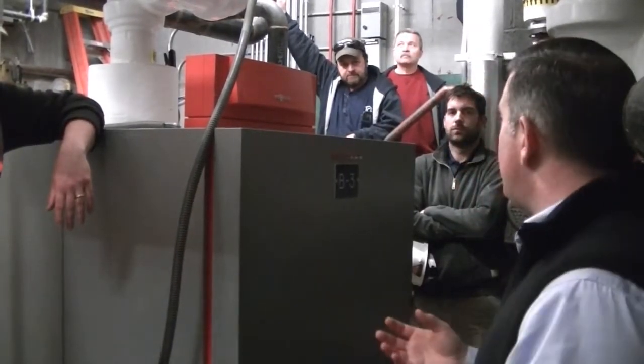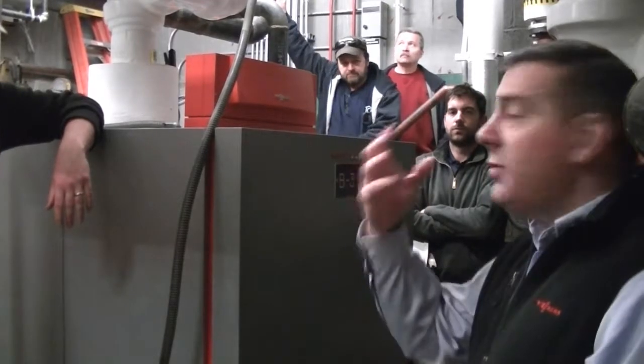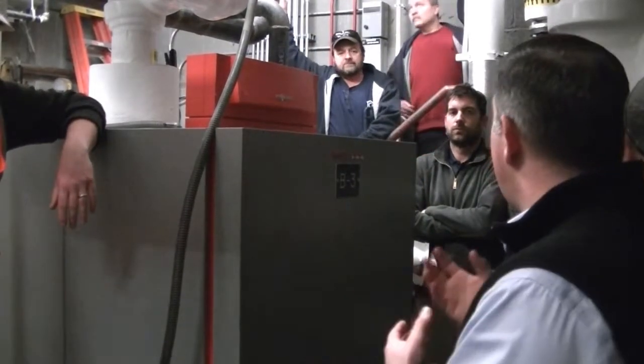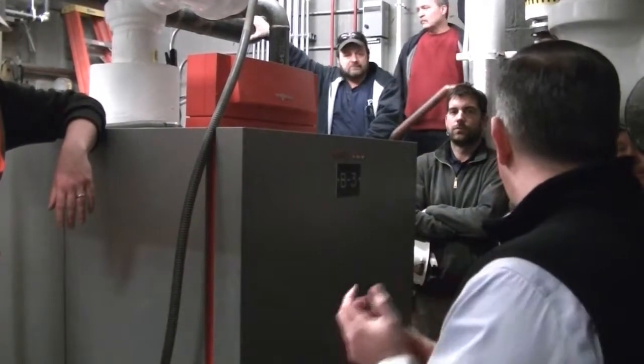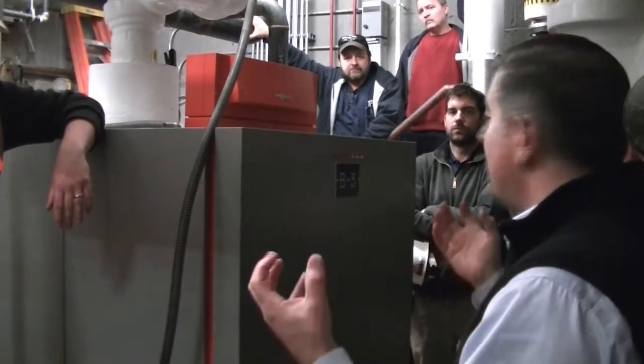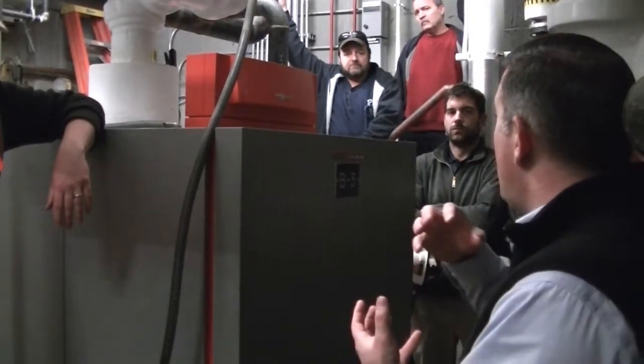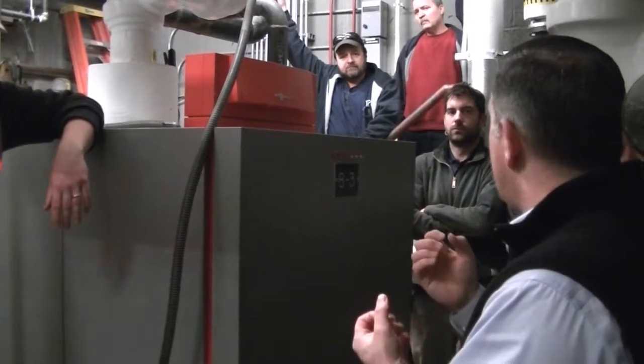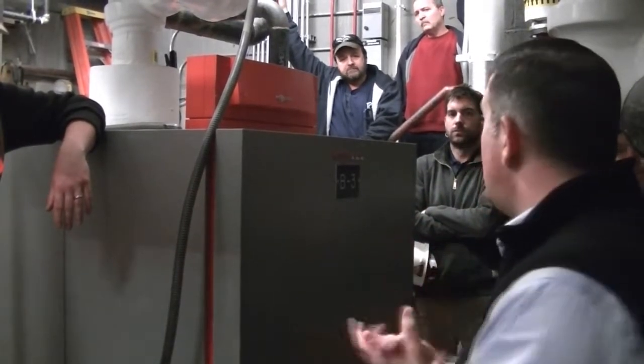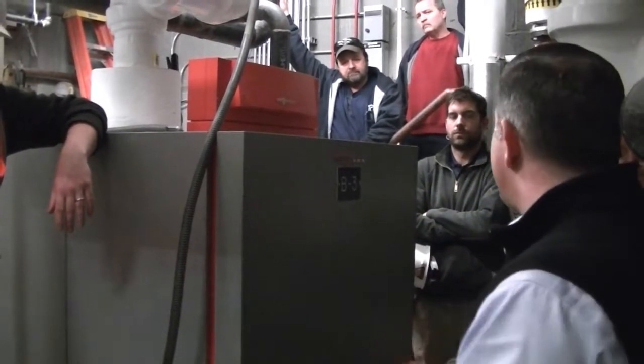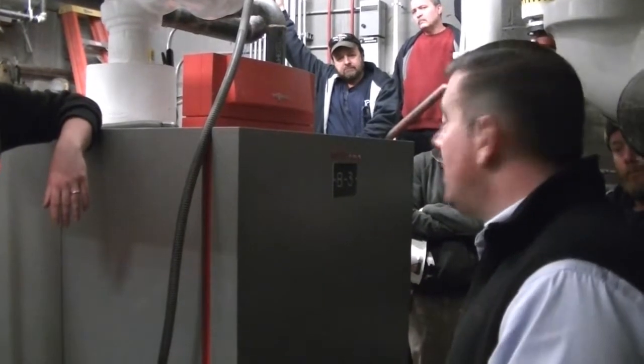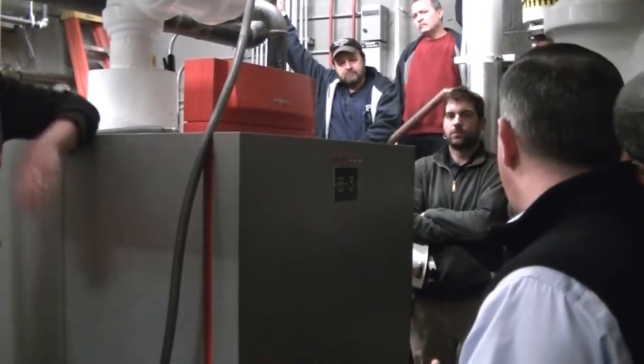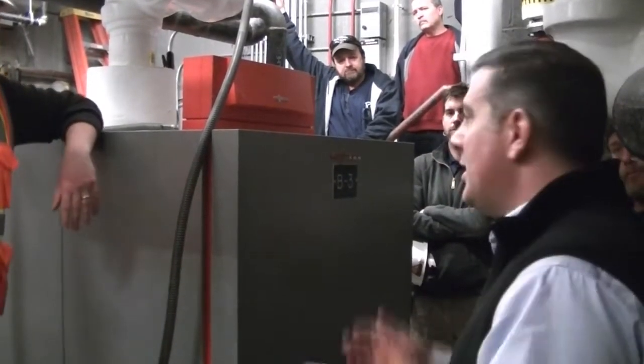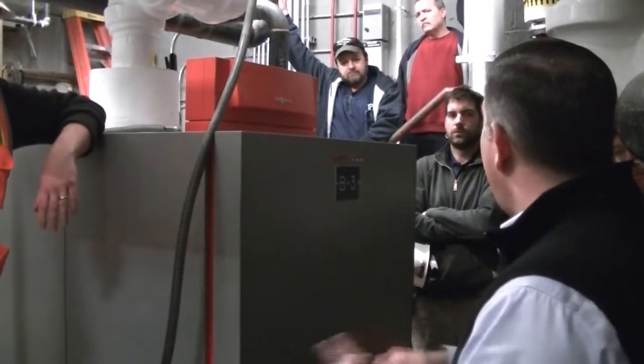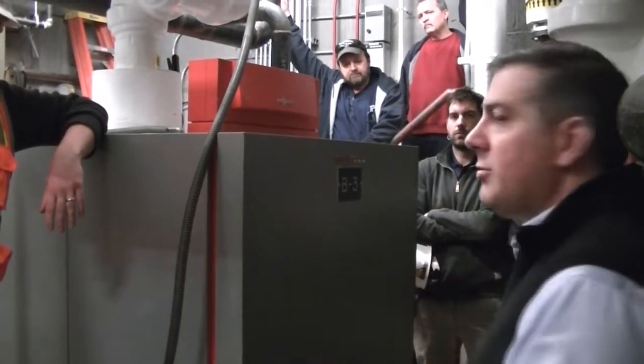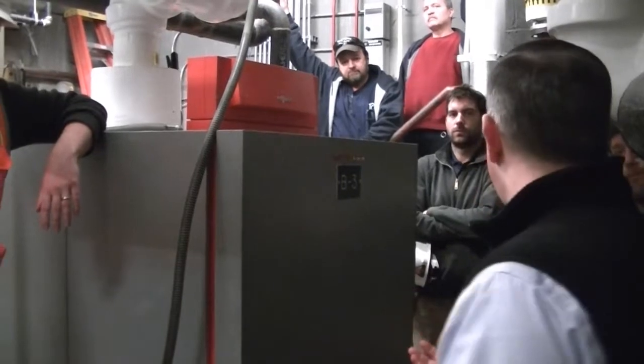These boilers are a little bit different. What we try to do is cool down those flue gas temperatures, because if we can get the flue gas temperatures down below, say, 130 degrees, we start to turn that water vapor, which was normally steam, back into a liquid, and we can reclaim some of the heat from those flue gases and put it back into heating the boiler. So instead of having a boiler that's somewhere in the 80 to 85% range at best, these boilers will operate somewhere in the 90, 95, 96% range, depending on what water temperature they're running at.